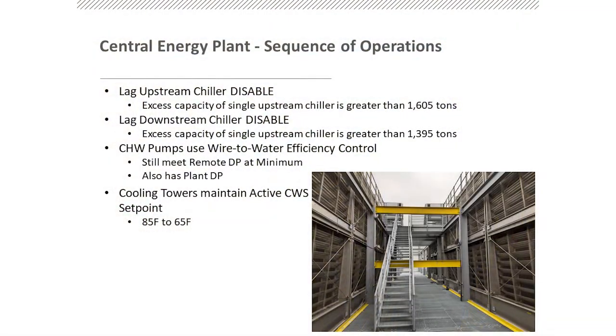When we first got out there, the BAS technician said they used the design number. Well, we already said later on we're going to talk about chiller plant testing at a low load, which probably means low delta T, which means a lot of extra flow. So we got to see a lot of times where 3 chillers were operating because they had that design flow. So we met with them, had discussions, and slowly tweaked that number up to try and minimize that third chiller turning on, because it caused some other issues that we'll get into later. And then finally, your upstream lag chiller is the same with the 42 degrees, and then you go on until you get to your 6 chillers operating.